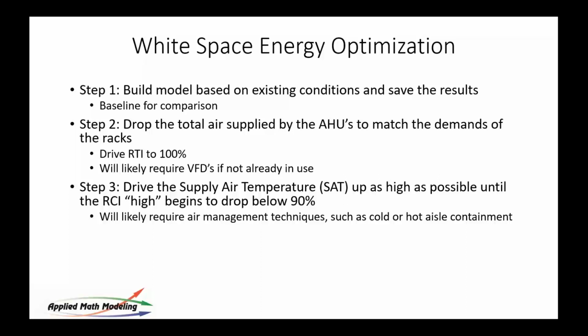RCI is the rack cooling index, and it is hot spots on the rack inlets. The TC 9.9 thermal guidelines suggest you shouldn't be higher than 80.4 Fahrenheit. Sorry for my SI guys, it's 80.4 Fahrenheit on rack inlet. And RCI just calculates how many of those areas you have. You want it to be in the high 90s if you can get it there. A few hotspots don't matter because you don't put equipment everywhere in the rack, but you certainly want it to be above 90. Typically it takes some air management techniques to get you there.